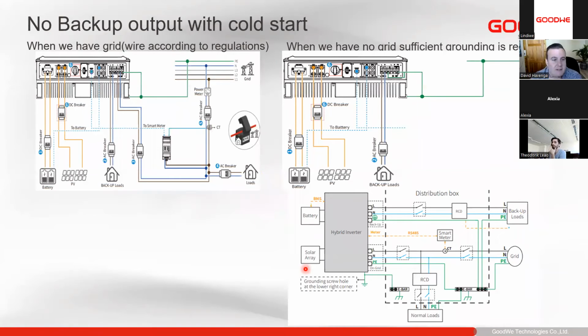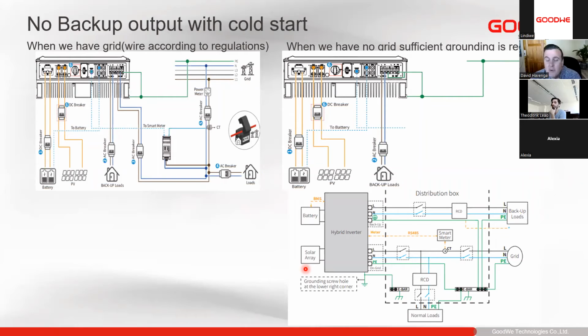This is a condition that happens sometimes. So if we are no backup with a cold start on inverters, especially the low volt inverters, sometimes they are used on sites that don't currently have utility. We always need to make sure that this grounding is correct. So even if there is no utility, as you'll see in this picture here, we need to make sure that there is grounding. So if obviously there's no utility, a ground or earth spike needs to be installed.